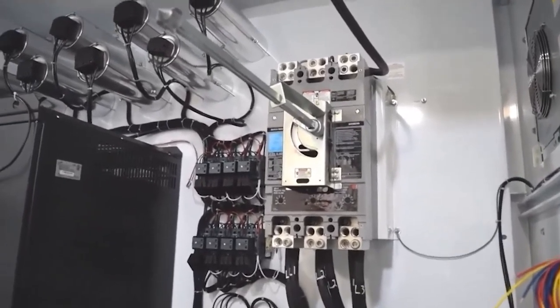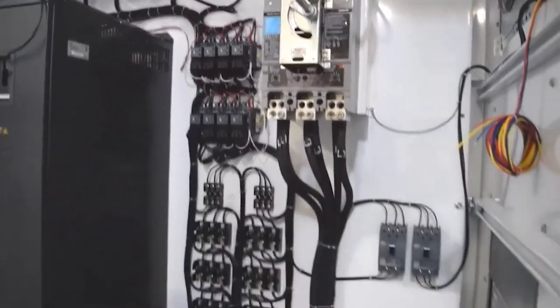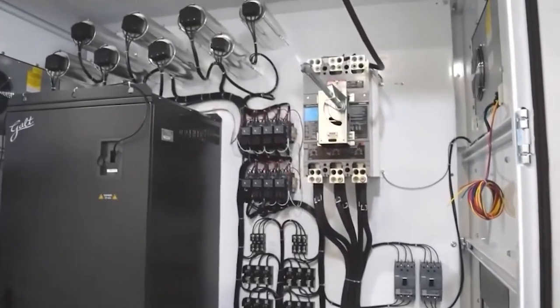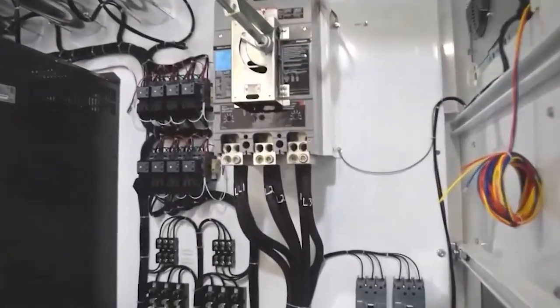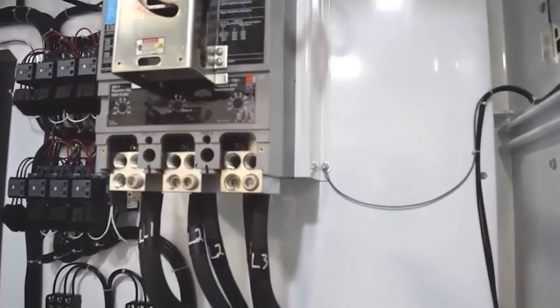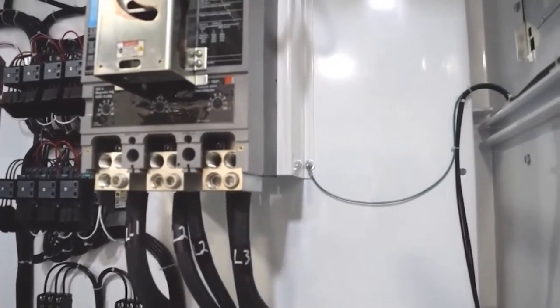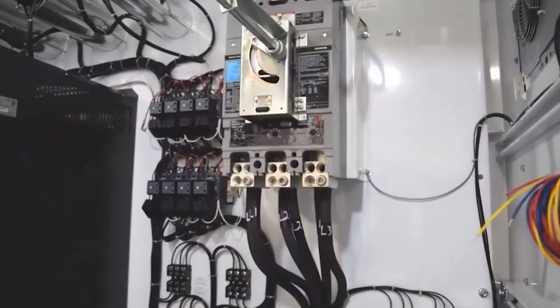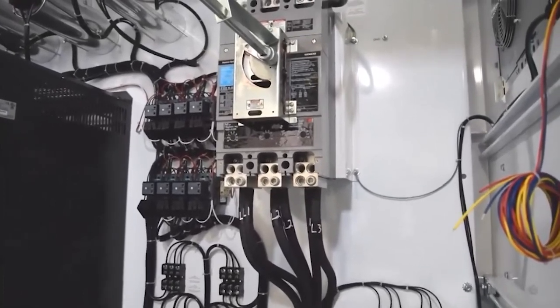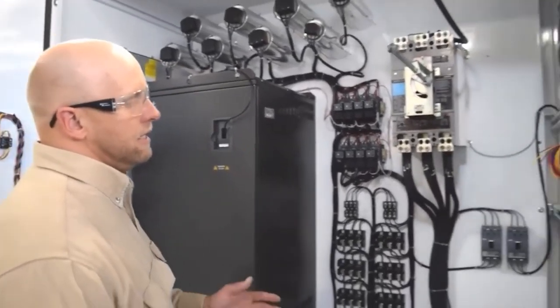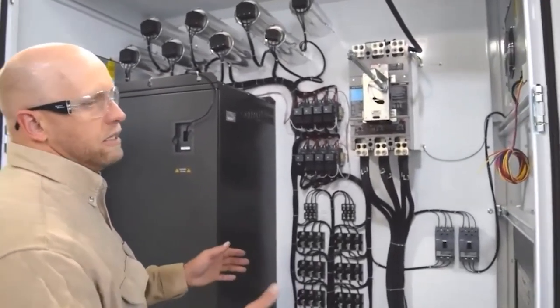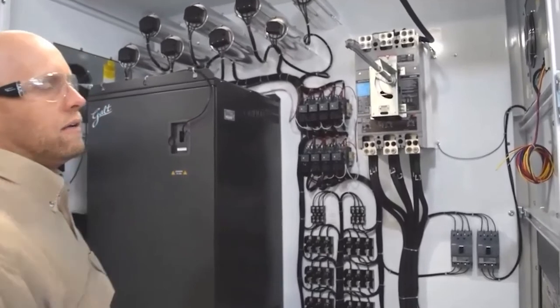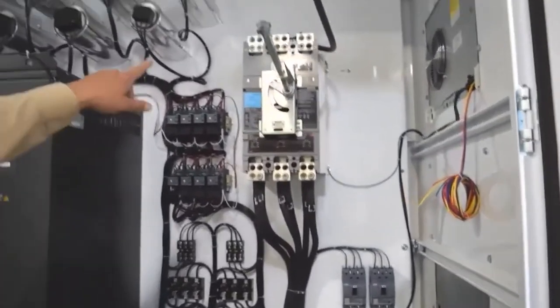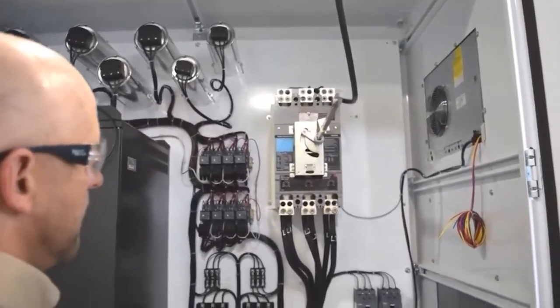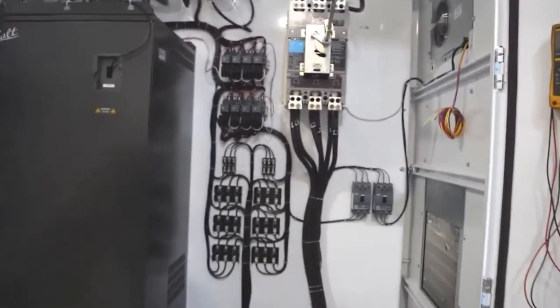So when you're looking at the breaker, as we get in and check it out, we always want to make sure we measure A to B, B to C, C to A to turn everything off, as well as measure it to ground as well. The reason that you do that is because if you have a switch that gets hung up, which has happened occasionally, you might open up 2 phases but not 3 phases and then find out the other one's live. So that's the reason that we always want to measure A to B, B to C, C to A, and to ground or neutral at the same time.